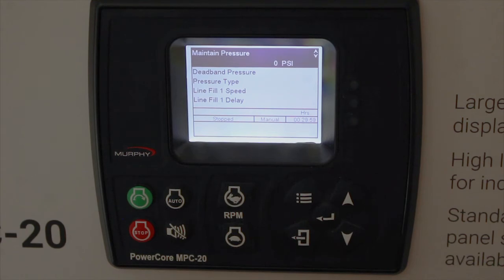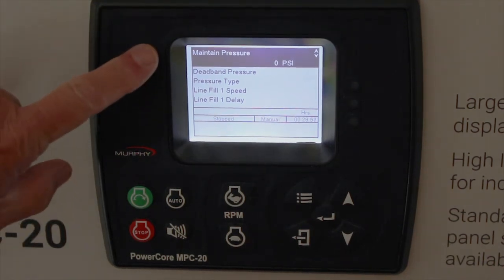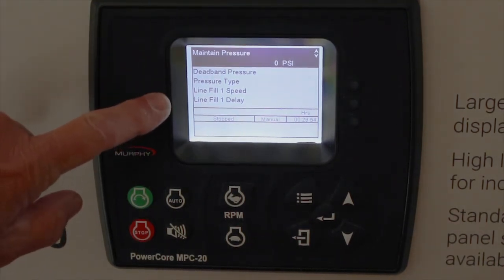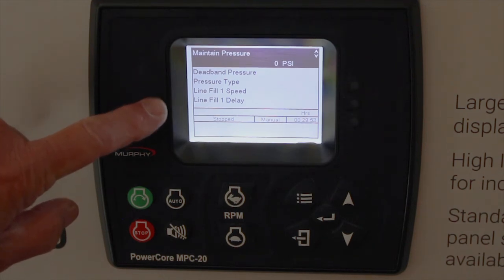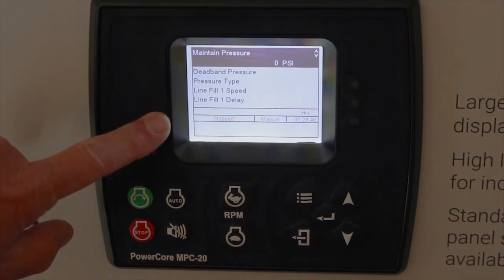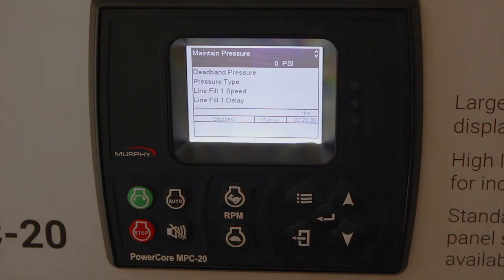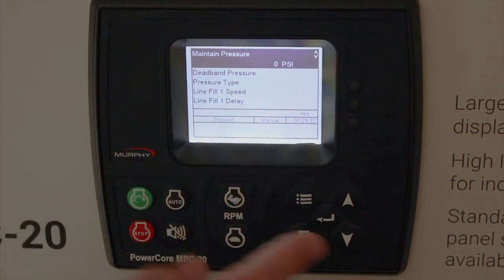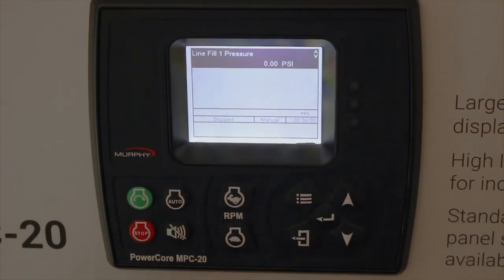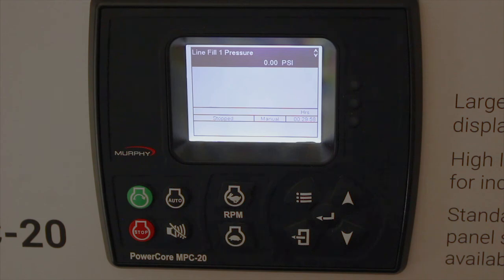Hitting enter reveals a maintained pressure set point, a dead band pressure type — whether discharge or suction — and a line fill feature. When filling a line that may be one or two miles long with air in it, you can hold RPM low to allow water to fill the line before throttling up to pressure. This gives you a line fill speed, a line fill delay, and a line fill pressure.